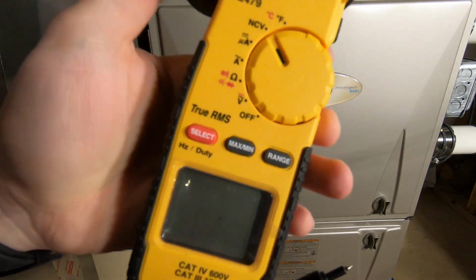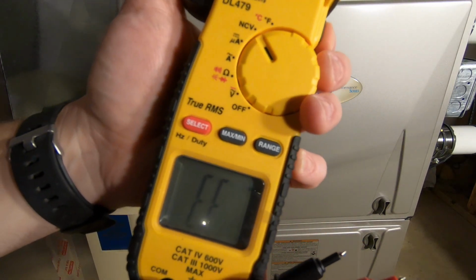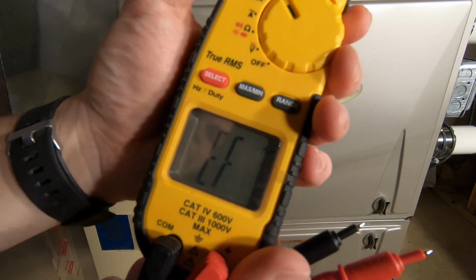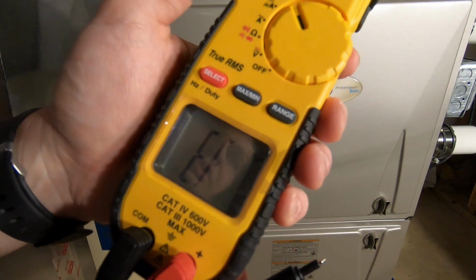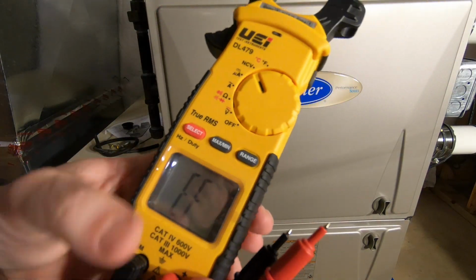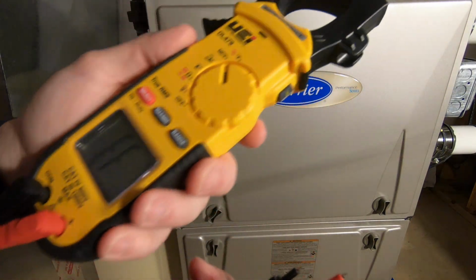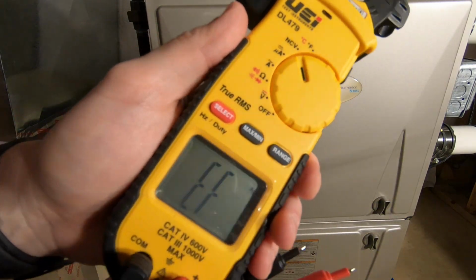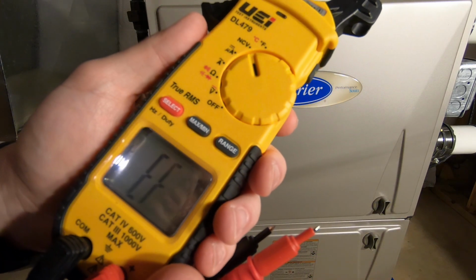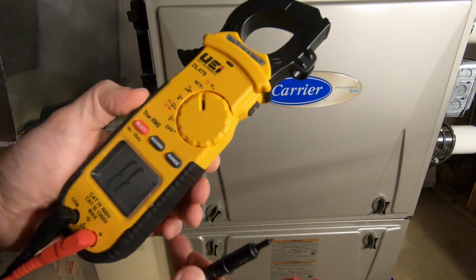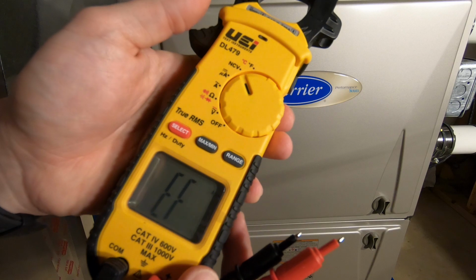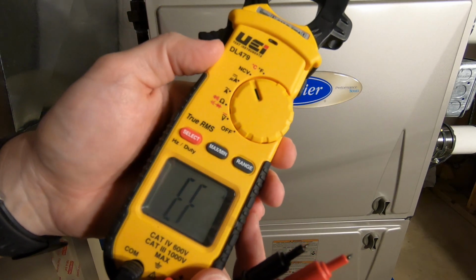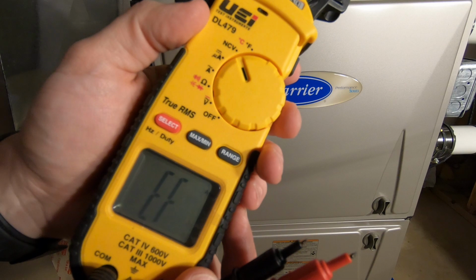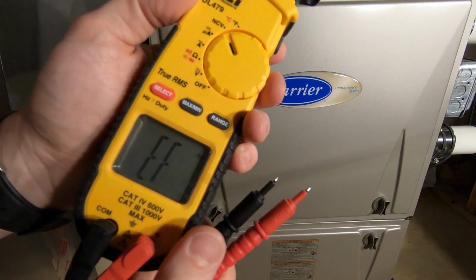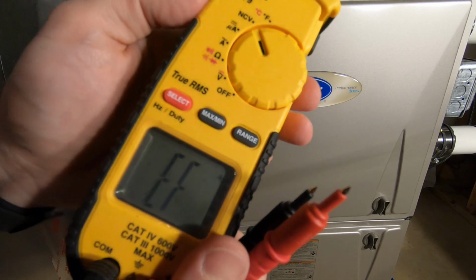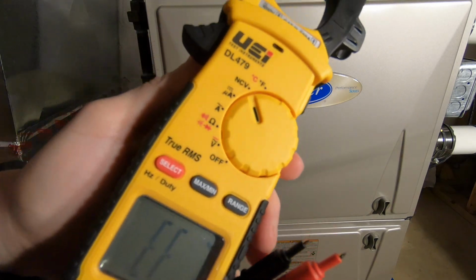Next, we have non-contact voltage. The light went out - the light's going to go out when it's non-contact voltage. This is where you would just take the unit and touch this part here to what you assume is a live electrical wire, and it should tone for you, meaning it'll display something, a tone from the meter telling you there's voltage present. However, if it doesn't, you still want to check with your actual probes to make sure before you go ahead and take it apart, because you don't want to be electrocuted.